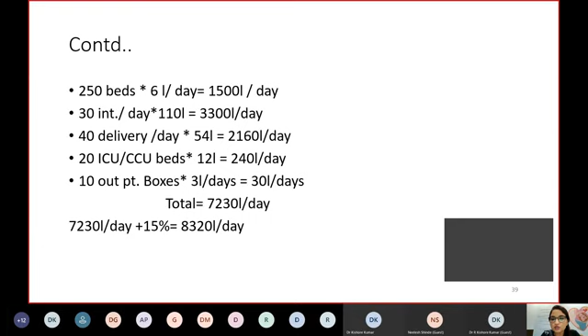Now we have to convert these liters into standard units, because the capacity of sterilizers comes in standard unit measurement. So I'm going to divide the 8320 liters by 54, because one standard unit is 54. By doing this, I get to know my standard unit requirement per day. It turns out to be 160. I'm saying that I've got a 12 hour shift, and one hour will be break time, so I will run 11 cycles. So 160 divided by 11 cycles means I have a requirement of 14.5 steam capacity per cycle. That is my rough estimate.